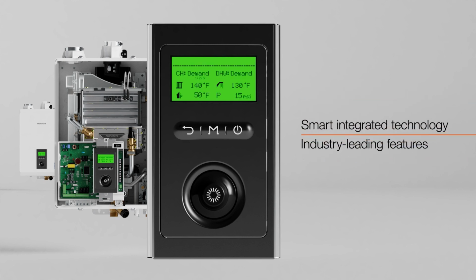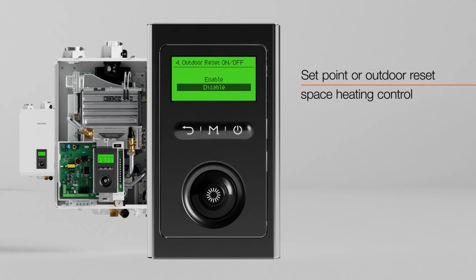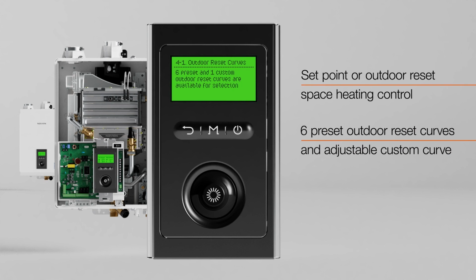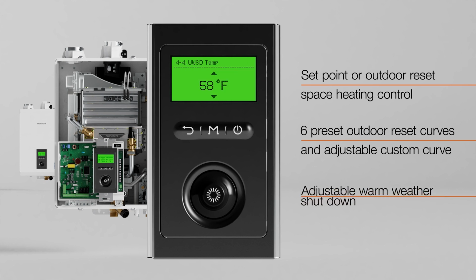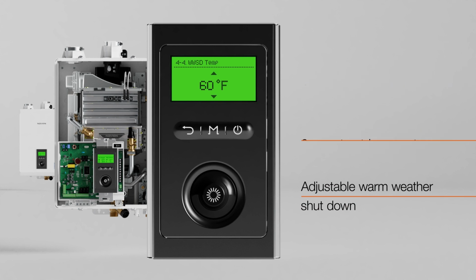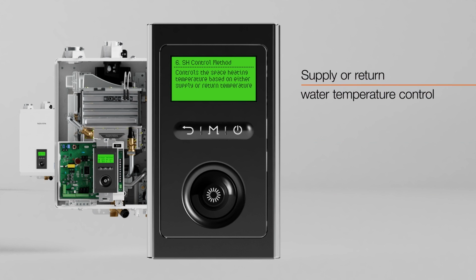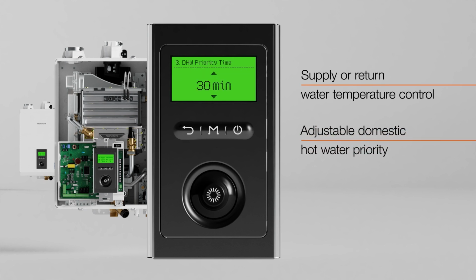With its smart integrated technology, the NHBH provides industry-leading features. A set point or outdoor reset control ensures precise and optimal temperature regulation, while 6 preset outdoor reset curves, along with the flexibility of a fully adjustable custom curve, suits a variety of heating needs. The boiler's adjustable warm weather shutdown feature prevents space heating operation during milder conditions. The option to control the supply or return water temperature gives the NHBH greater ability to balance control and efficiency. The NHBH also boasts an adjustable domestic hot water priority, ensuring that the domestic hot water demand can be maximized while still providing proper space heating.